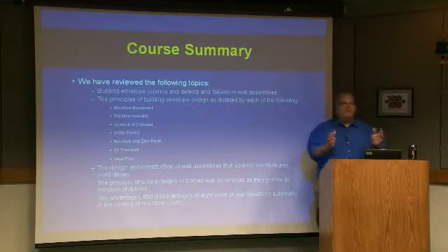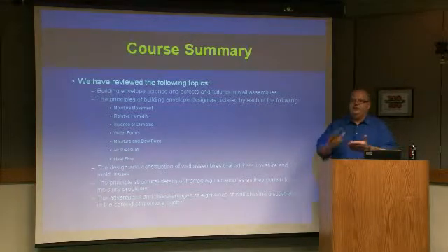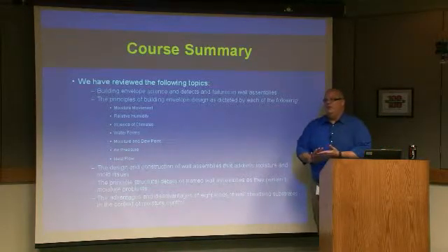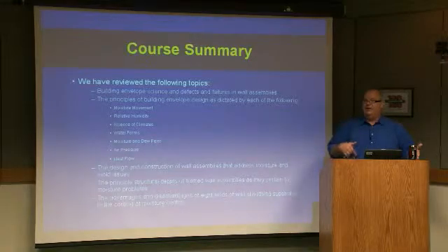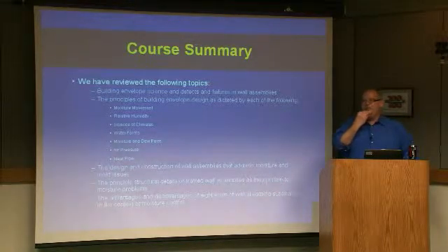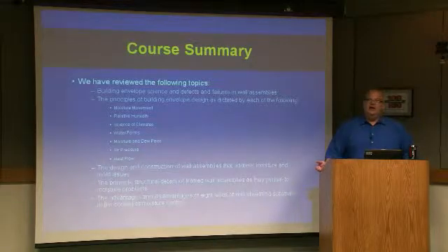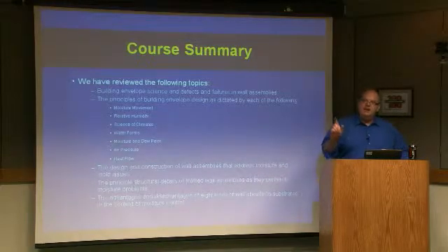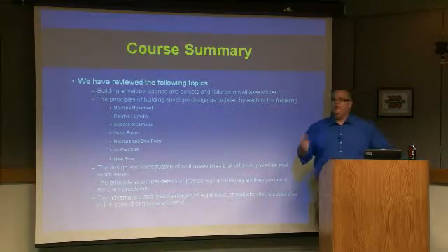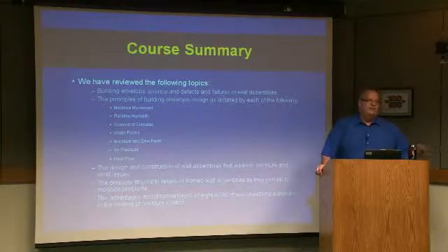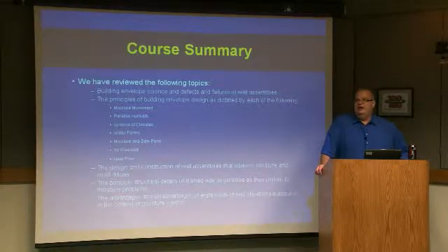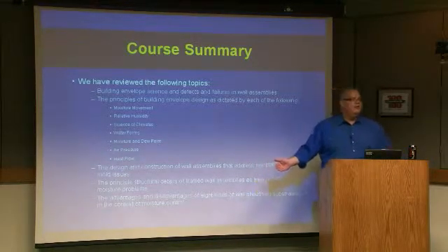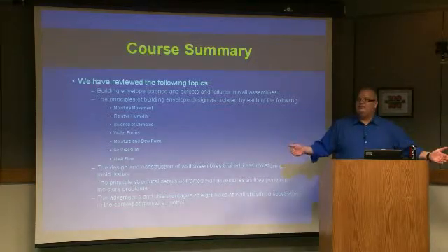What you don't want is water getting between the two. If you have two materials that are resistive and they're adhered to each other, or side by side, there's no way for water to get in between, so you've essentially got one resistive layer. What we worry about is when we split it, and now water can get in between the two. And this is the catch-22 of using OSB or plywood sheathings. The building code gives you very specific instructions about how to measure a vapor retarder. It never tells you to measure your sheathing. If you measure your sheathing according to the building code, what you find out is, I've got bad news for you: if you're using OSB or plywood, you're using a vapor retarder. So if you use OSB or plywood in a house and you use an interior vapor retarder, boom, you've broken a cardinal sin. You created two vapor retarders with a big space in between where water's going to go.